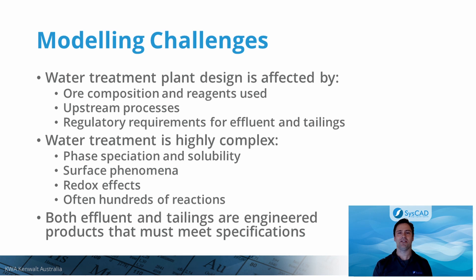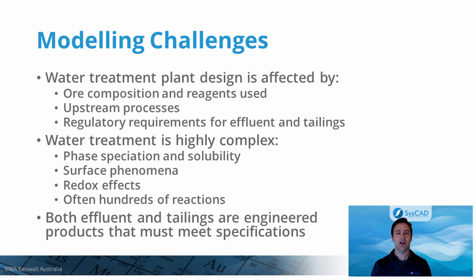A water treatment process design is affected by ore composition, reagents used, upstream processing routes, regulatory requirements and other factors. Mathematically describing water treatment requires models for multiphase equilibrium, speciation, multicomponent solubility and heterogeneous adsorption to solid precipitates. Simulation of a typical water treatment process for a real mining water solution can involve hundreds or thousands of reactions. SysCAD with the TCE add-on simplifies the application of best available data for this challenging problem.